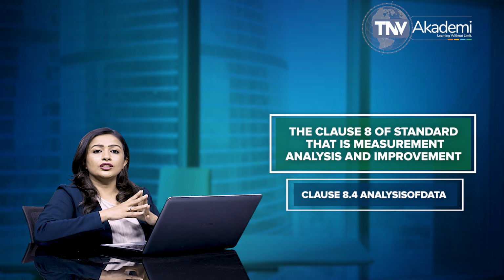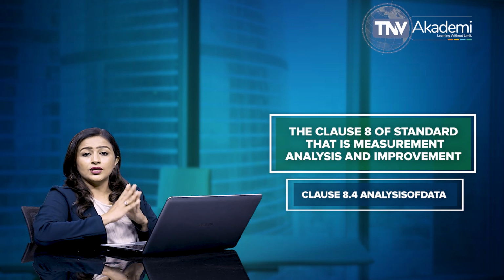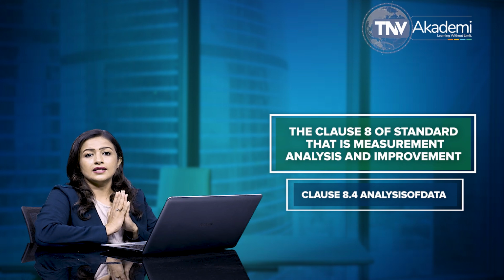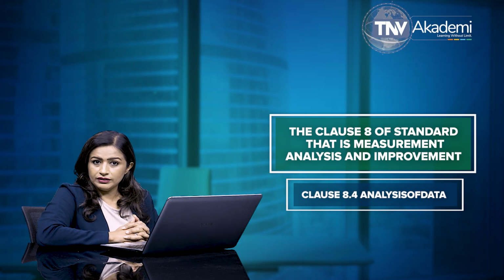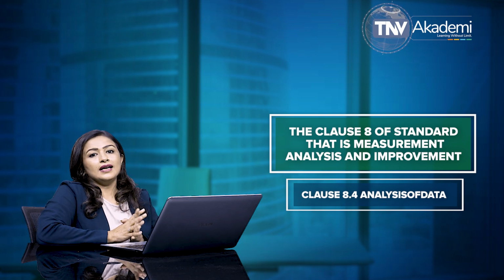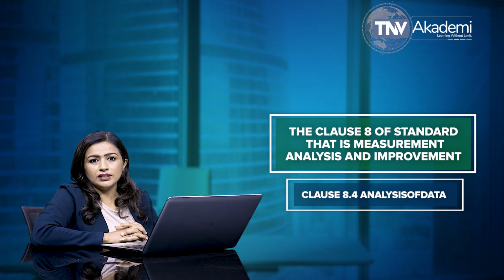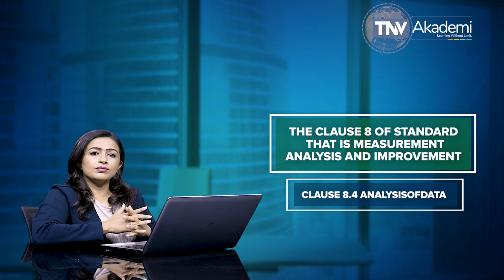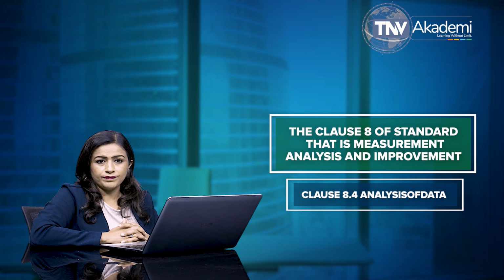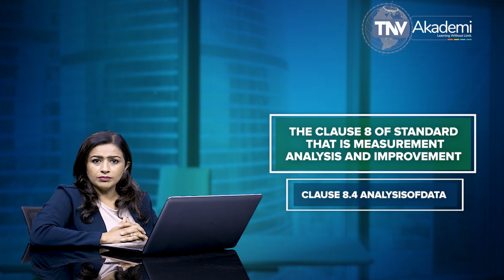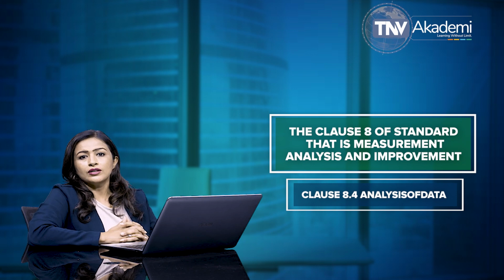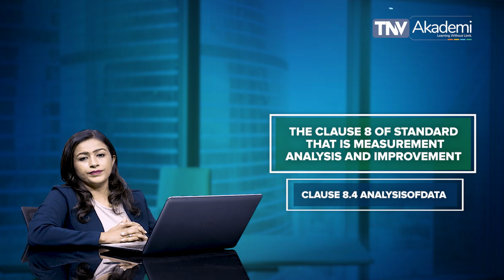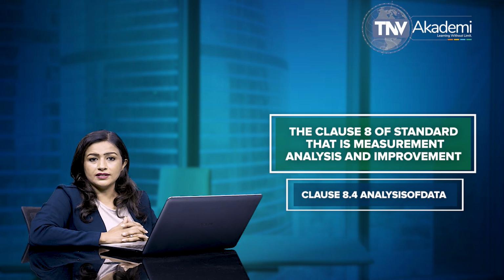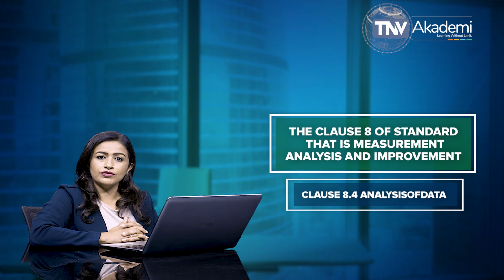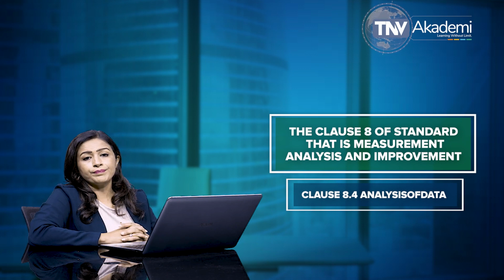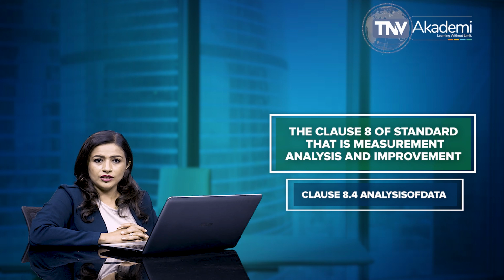The procedures must include determination of appropriate methods, including statistical techniques and the extent of their use. Further, clause 8.4 says that the analysis of data must include data generated as a result of monitoring and measurement and from other relevant sources. The data must include, at a minimum, input from feedback, conformity to product requirements, characteristics and trends of processes and products, including opportunities for improvement, suppliers, audits, and service reports as appropriate.